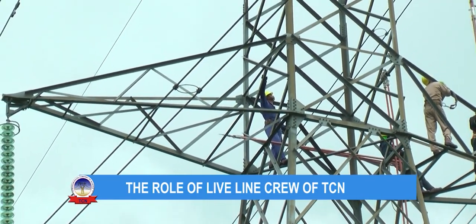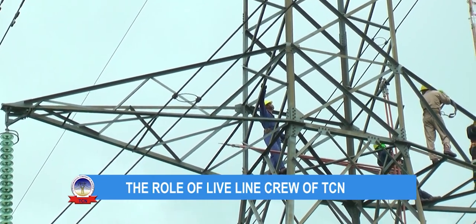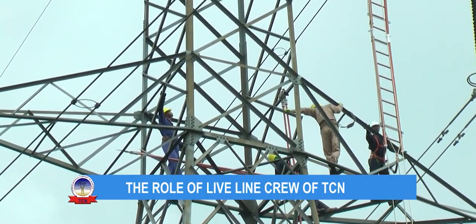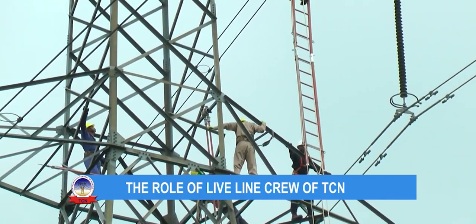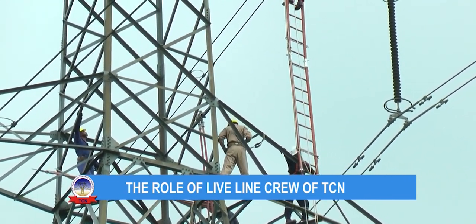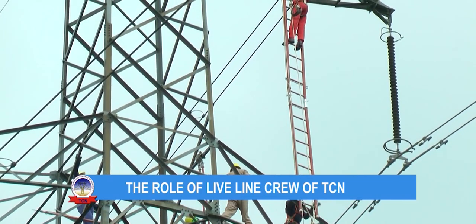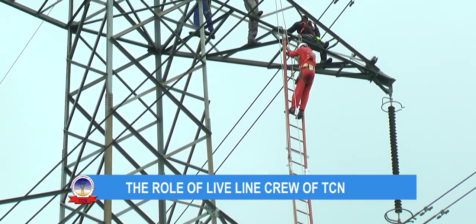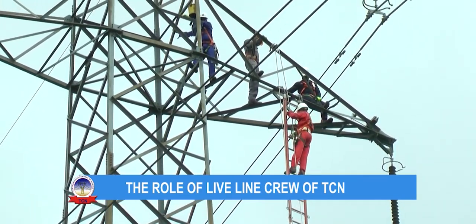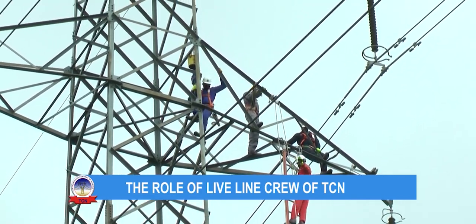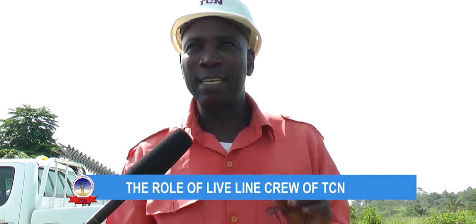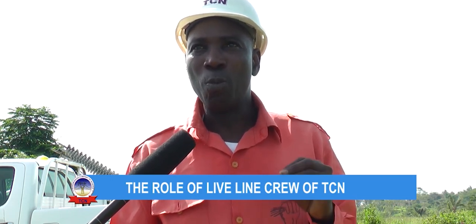Here, we handle corrosion due to our temperature and atmosphere. The lines, conductors, and insulator spindles are prone to corrosion. When corroded, it detaches, and when it detaches, it causes tripping to the system or to the grid entirely. To avoid that, management has sent us here to change glass insulators to polymer composite insulators, to avoid that constant corrosive insulator issue.